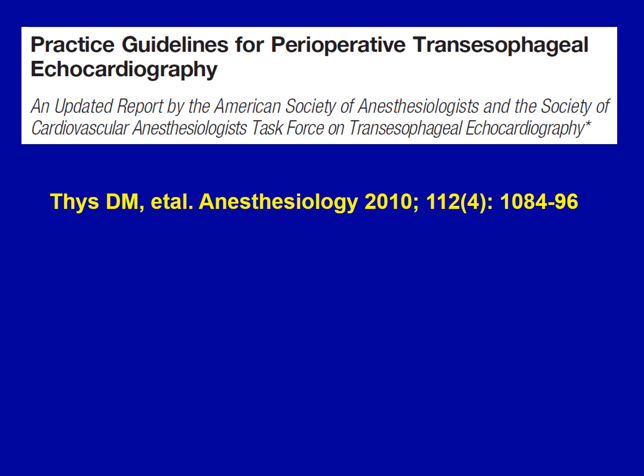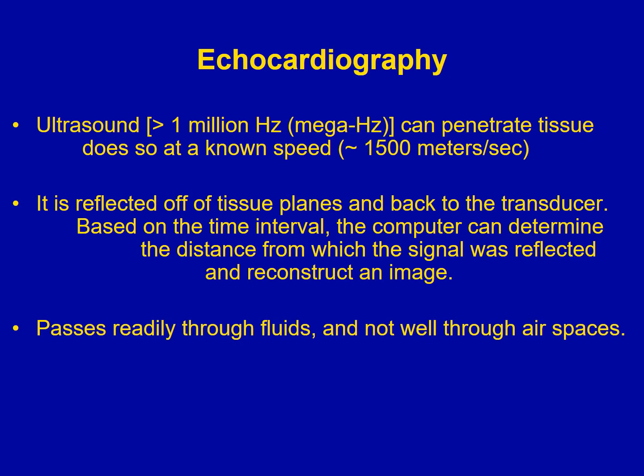The ASA guidelines is something you should be familiar with and have in your bibliography, in your list of papers, which is somewhat dated, but still is appropriate, and you should be familiar with it. Ultrasound, although it means above hearing, in practicality we're talking about more than 1 million hertz, or 1 megahertz, and is unique in that it can penetrate tissues at a known speed of around 1,500 meters per second. It is reflected off of tissue planes back to the transducers, and based on the time interval, the computer can calculate the distance where the signal was reflected from and reconstruct an image. It readily passes through fluids, but not so well through spaces.